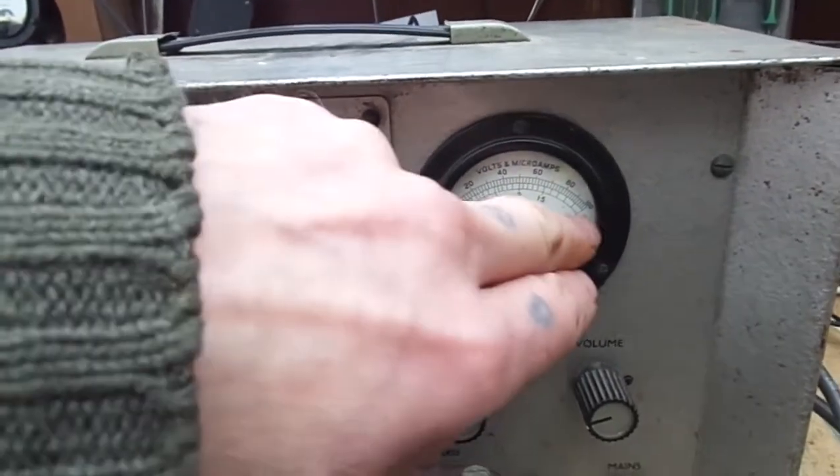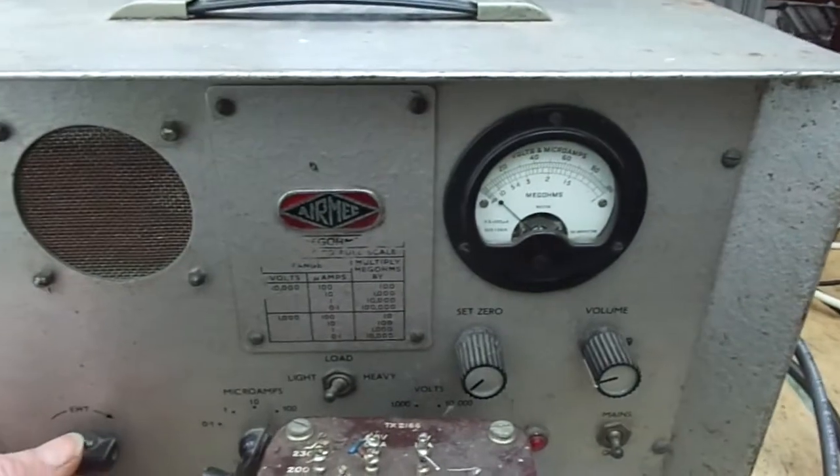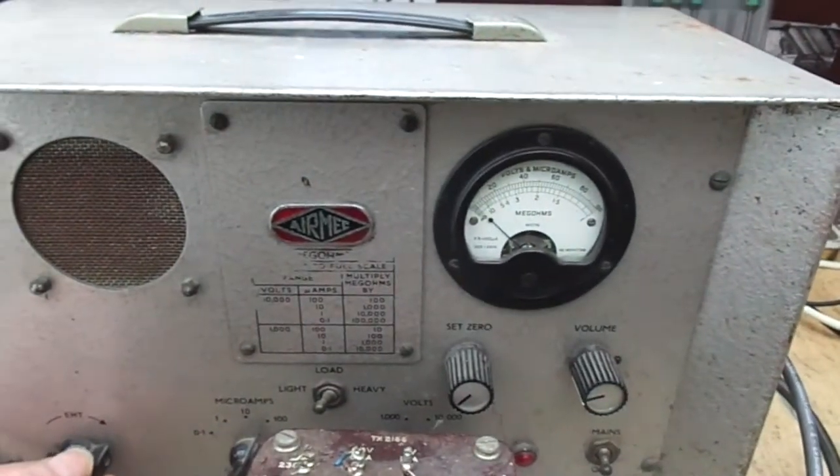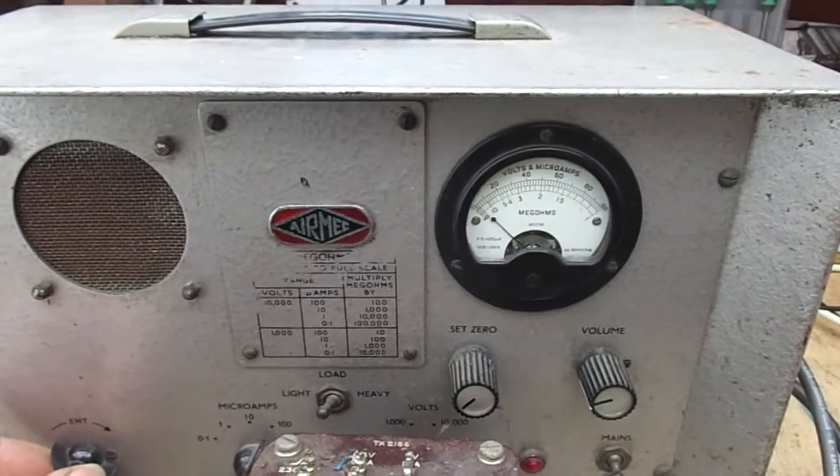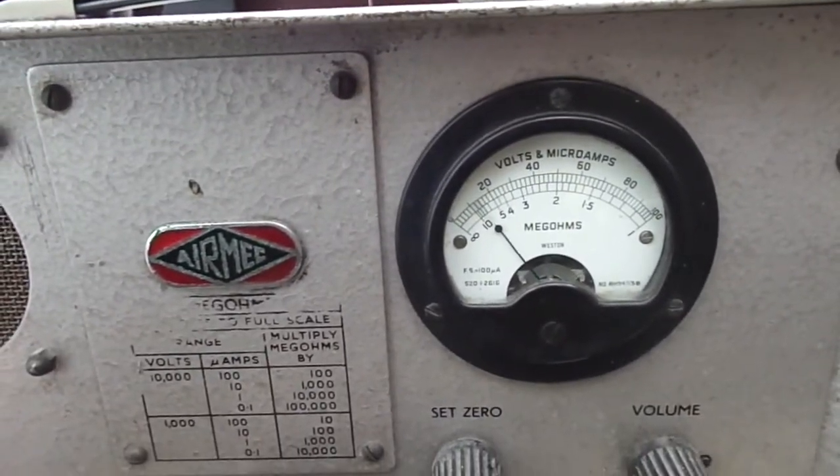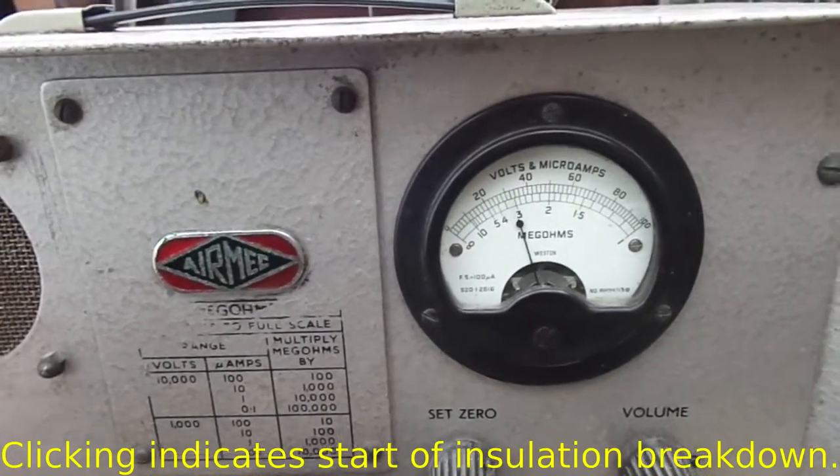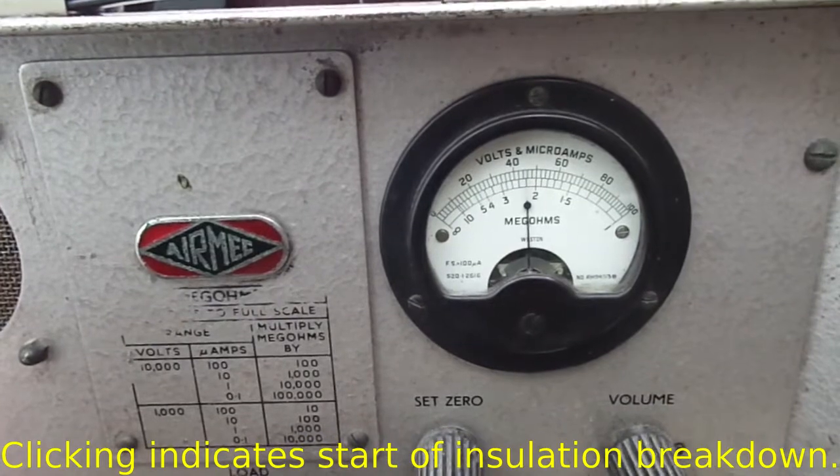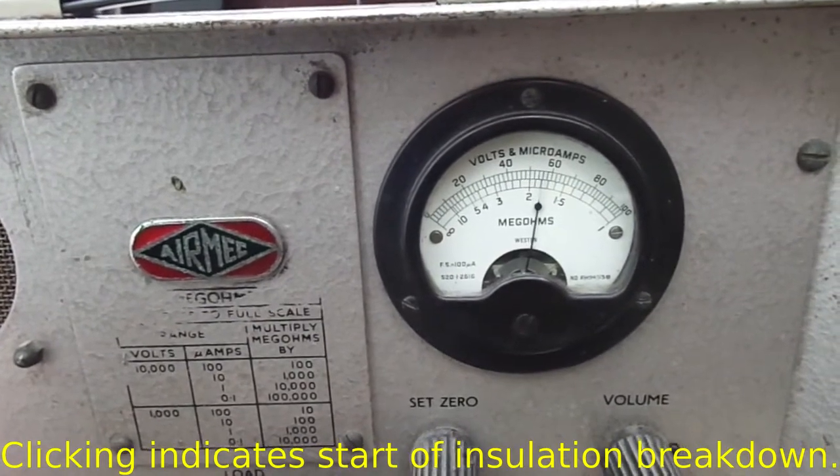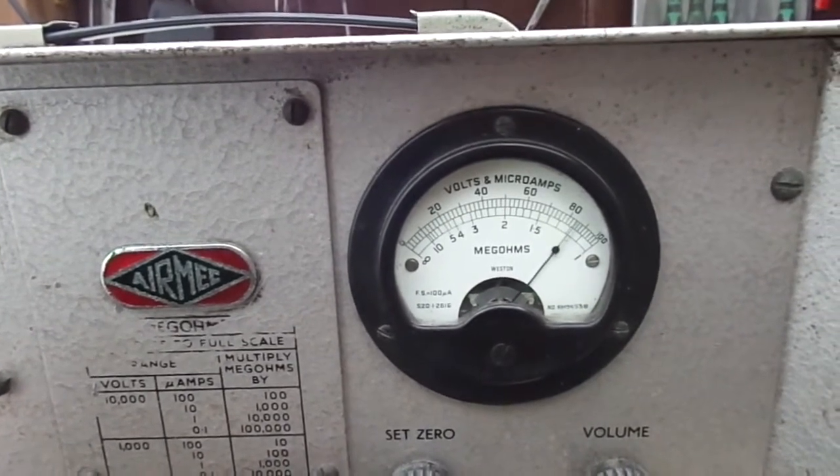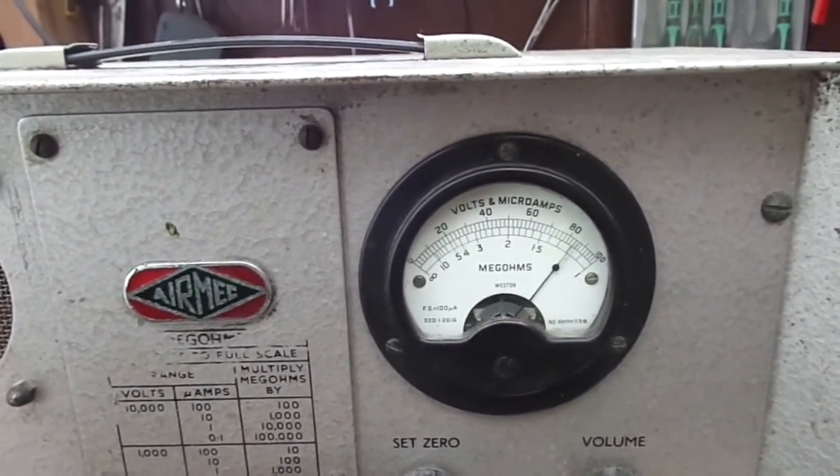When we turn the voltage up you'll notice that if it's really good insulation it will stay up here. If the insulation isn't so good it'll go down this end. Let's crank it up. We're on 10,000 volts at 100 microamps. Point here.